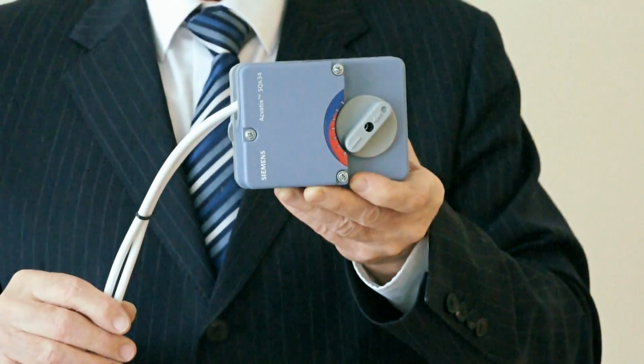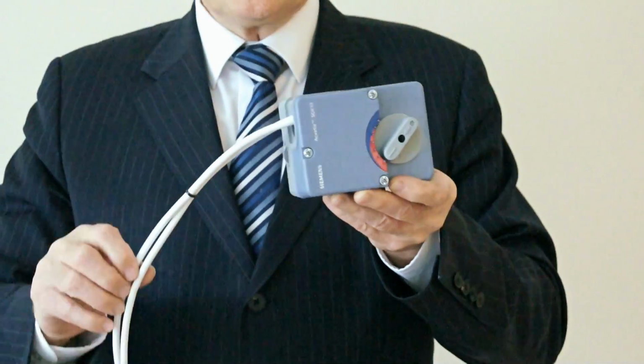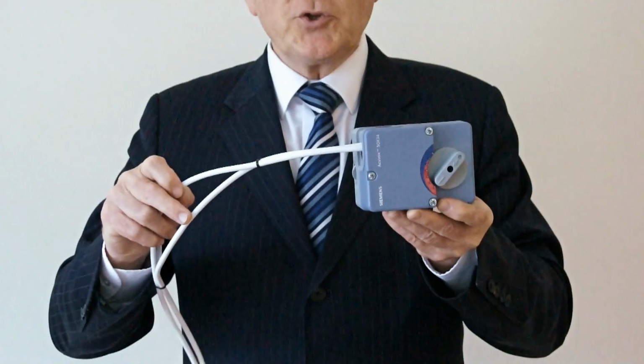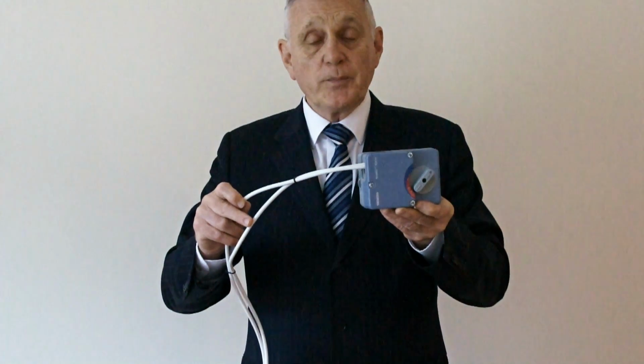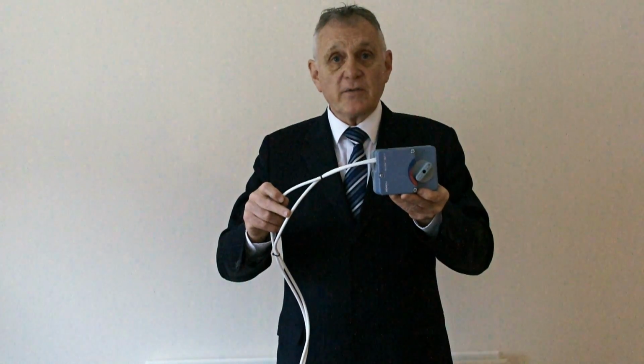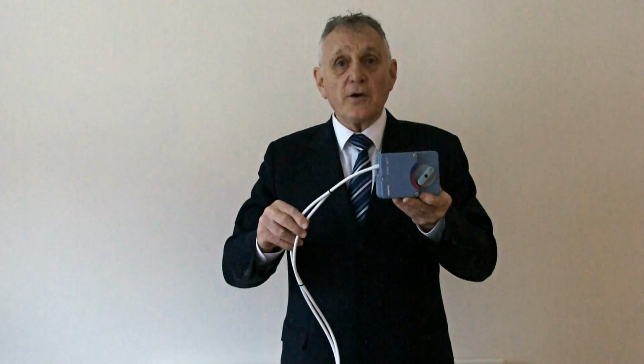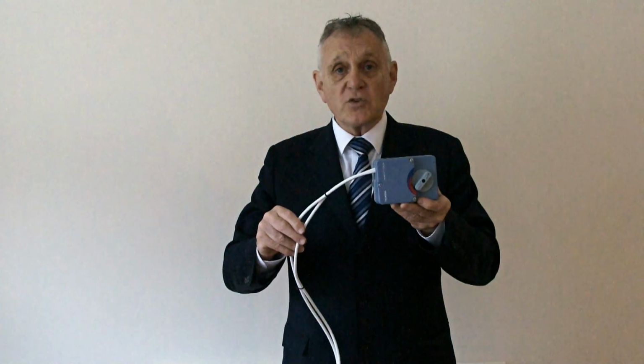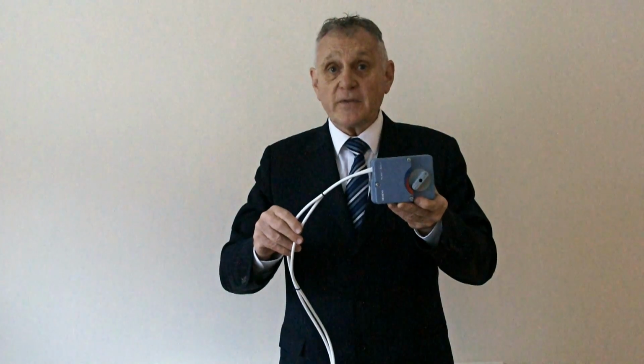Now these actuators can be controlled either via two wires, which requires two relays within the HeatingSave system, or alternatively by a 0 to 10 volt supply, which HeatingSave can also provide. In both cases there's something called a PID algorithm which manages this, and later on we'll see that on the graphs of the software to see how well HeatingSave actually does the job.